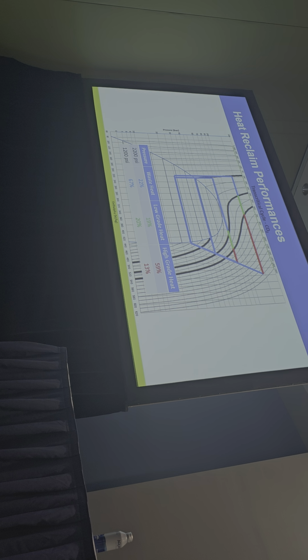and as soon as you have less flash gas, you improve the COP. The other thing which is really nice, when you're playing with the pressure, you're also playing with the amount of heat rejection, and the quality of the heat rejection in terms of percentage. The higher the pressure is going to be, the more high temperature heat reclaim I'm going to have. Then it's a question of how much do I need, and where do I want to put the pressure to make sure I have the most efficient COP.